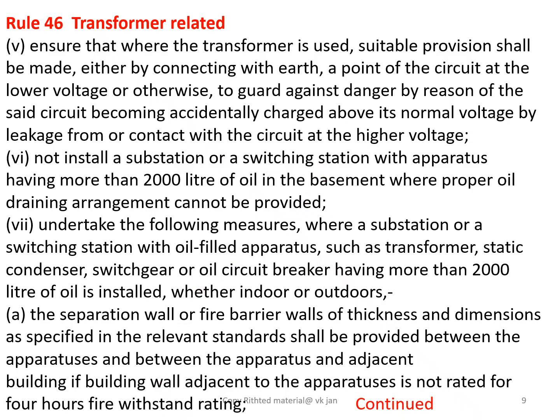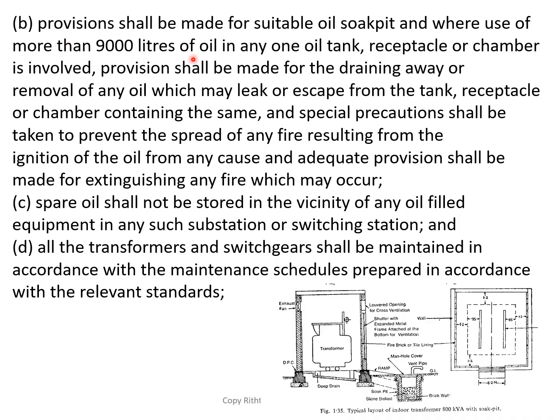To be continued. Friends, provision shall be made for a suitable oil soak pit, and where use of more than 9,000 liters of oil in any one of the oil tanks, receptacles or chambers is involved, provision shall be made for drainage away or removal of any oil which may leak or escape from the tank. Tank means transformer oil tank. Receptacle or chamber containing the same, and special precautions should be taken to prevent the spread of any fire resulting from the ignition of the oil from any cause, and adequate provision shall be made for extinguishing any fire which may occur.